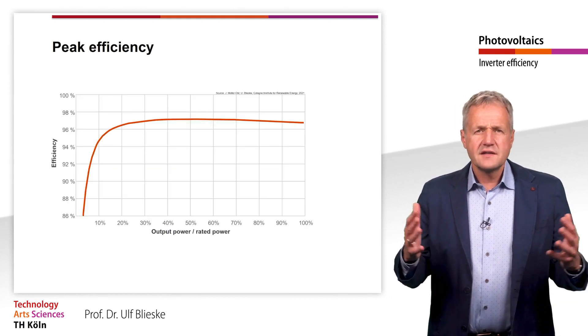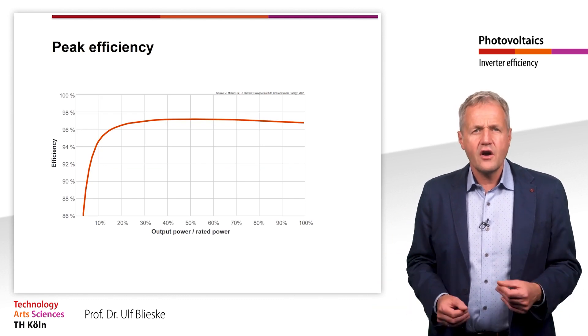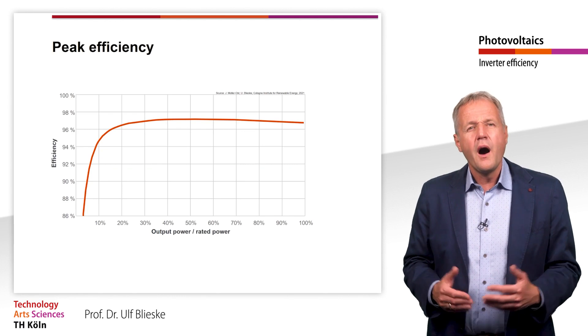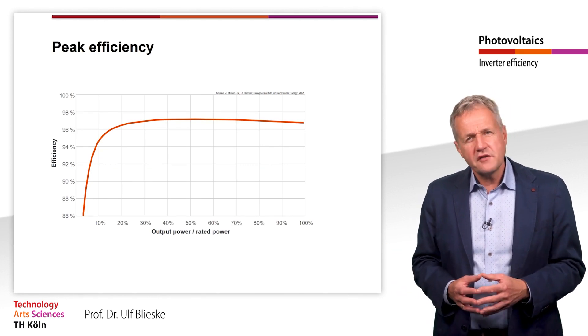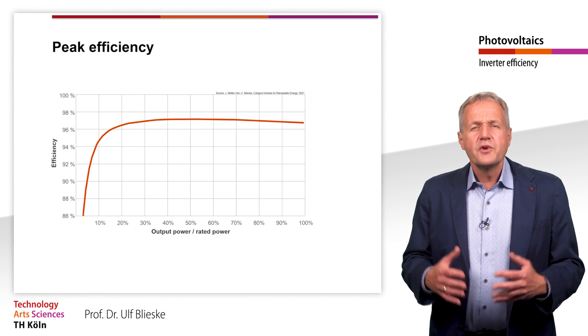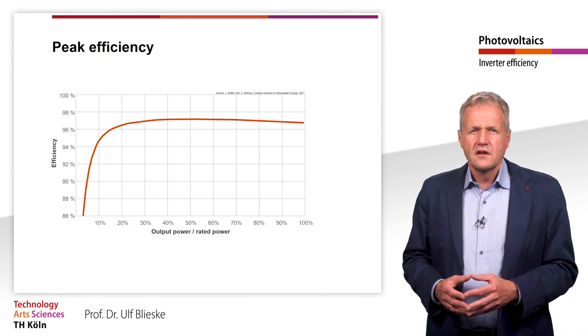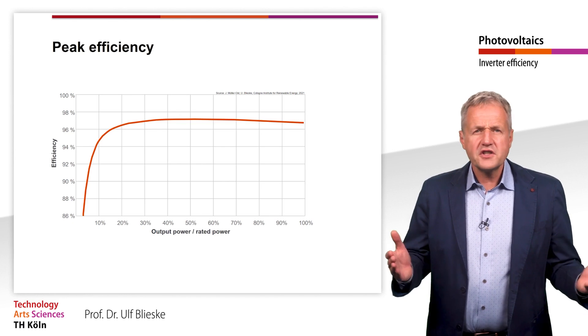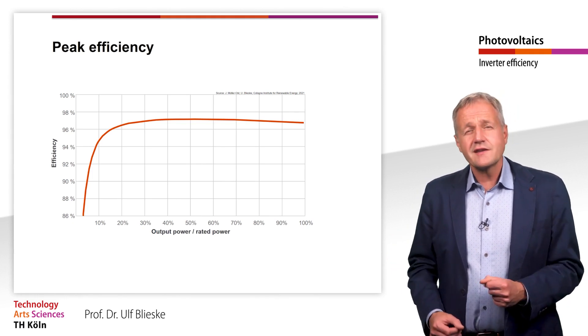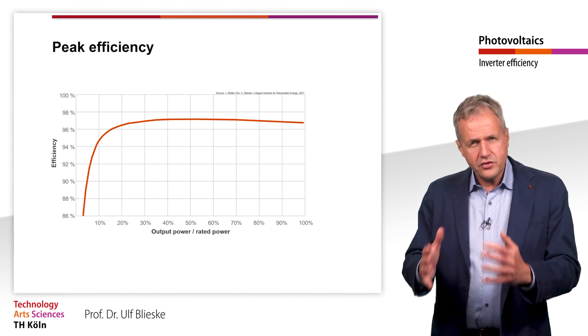In the datasheet of an inverter you will usually find an indication of its maximum efficiency. However, this peak efficiency is only achieved with a very specific input power and voltage. The efficiency is not constant, but depends significantly on the input power and the input voltage.